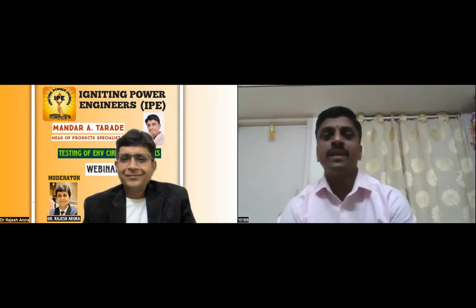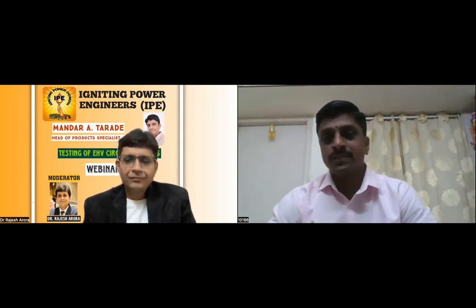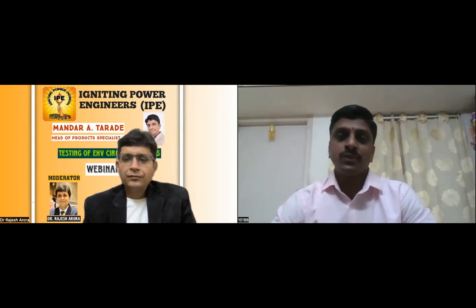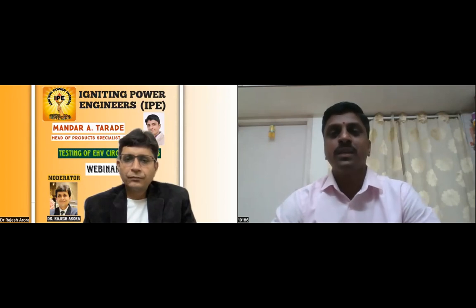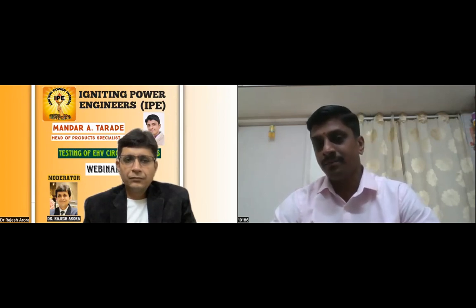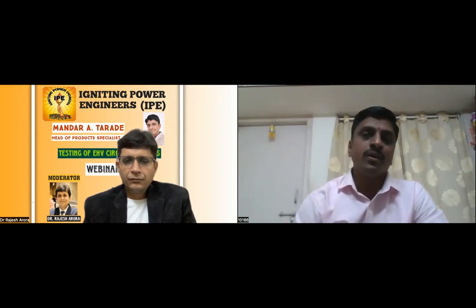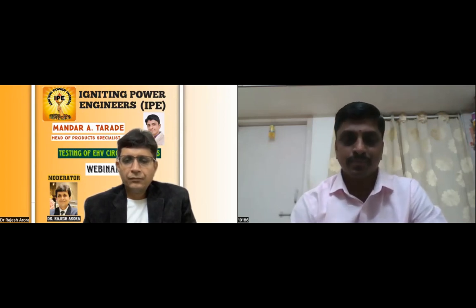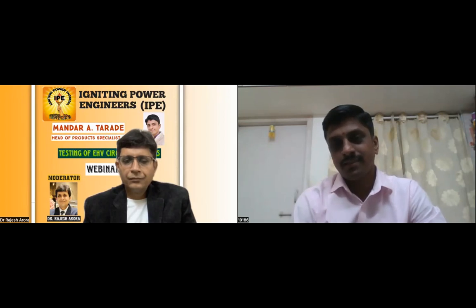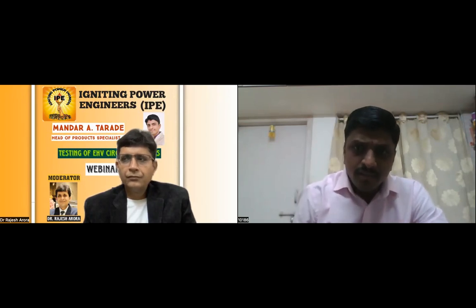Sir, opening is very critical because whenever there is a fault, it is expected that your breaker should not allow that fault to pass to your critical devices like the transformer or the CT. Because of that, your opening time is always less. I already highlighted that your opening time is always in the range of 15 to 35 milliseconds only. Is there some measurement technique that makes it that different?